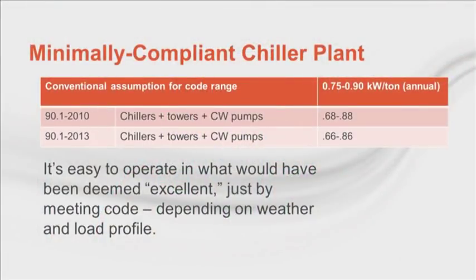If you turn the crank on an energy model, the minimally compliant water-cooled chiller plant, just meeting 90.1 2013 requirements and using good design practice for decisions where there are no requirements, leads to a chiller plant that will be quite good in annualized energy consumption, in kilowatt hours per ton hours. In reality, though, there is no certain answer to how well the typical new chiller plant actually operates today, even if it does meet code.